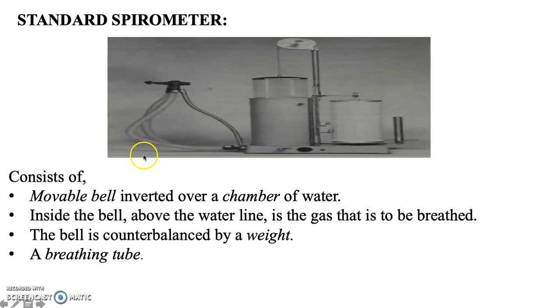That gas has to be breathed by the patient. So you will have a moving bell and a chamber of water, and inside the bell you will have a gas, and that gas will be breathed by the patient. When the patient inhales and exhales, the bell will be moving. To overcome that movement, the bell is usually counterbalanced by some weight mechanism, and for that you will have a pulley-like arrangement. You can see it here. And then you will have a breathing tube. With the help of this tube, the patient will be inhaling the gas.